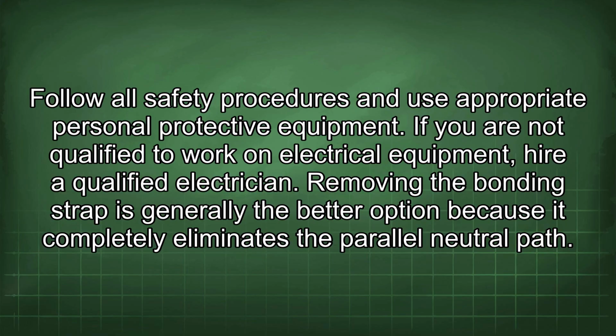Removing the bonding strap is generally the better option because it completely eliminates the parallel neutral path. However, it is crucial to get approval from the manufacturer because removing the bonding strap might affect the product's UL listing. The second option, removing the EGC, is okay, but it should be the last resort. The EGC is there for a reason, and that is to protect people.